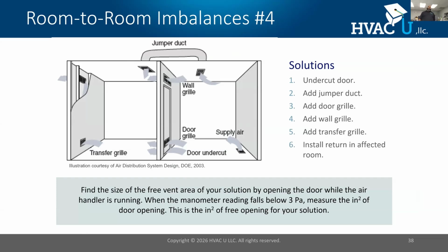How do you fix it? In most cases, we fix it by trying to get return air back to the air handler. Oftentimes it's a return problem more than a supply problem. Some of the solutions would be to undercut the door. You would take some off the bottom of the door, but you lose your privacy, so it's not the best solution. You can add jumper ducts. Jumper ducts are located here in the attic.